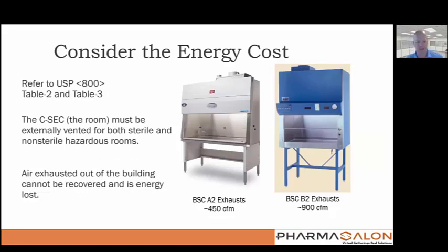So let's consider the energy costs, right? We've already established on tables 2 and 3 that we must externally vent the CSEC. And part of that on the hazardous side in our ISO 7 hazardous buffer is this biological safety cabinet, right? The reason I bring this up, this is important to see, is if you look at this first category, it's called a BSC A2. And A2 has a 70-30 interior recirculation, which means 30% is getting exhausted, 70% is getting recirculated.